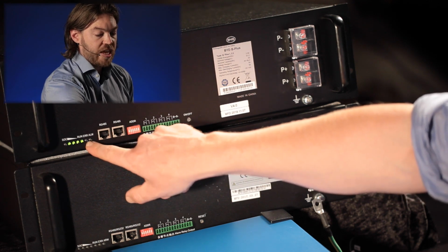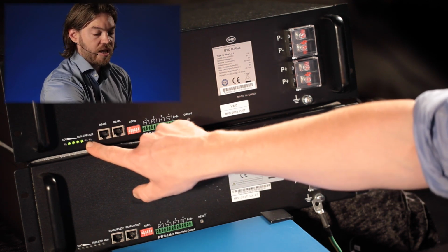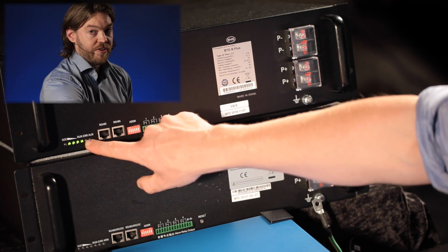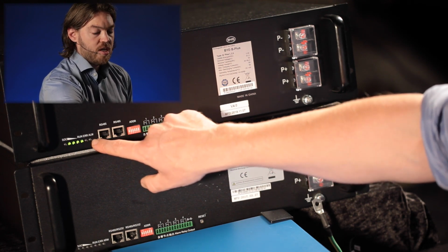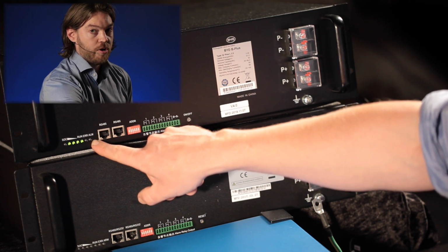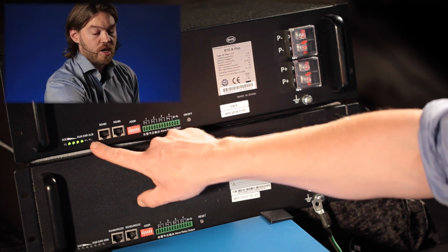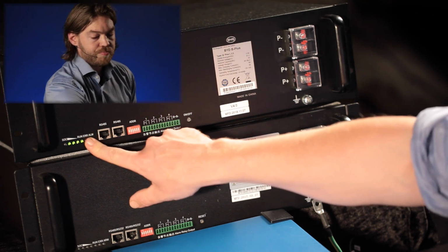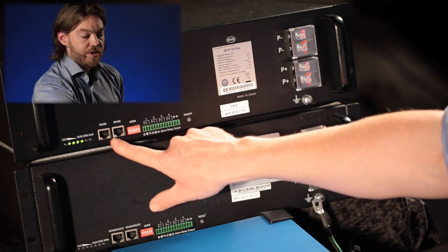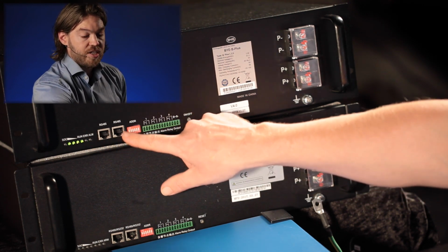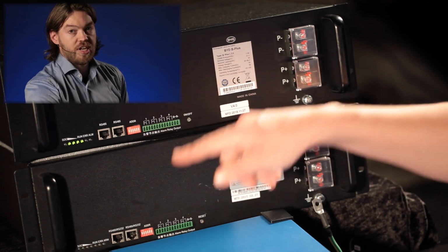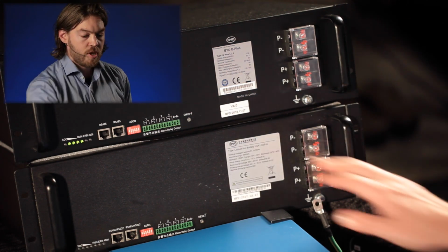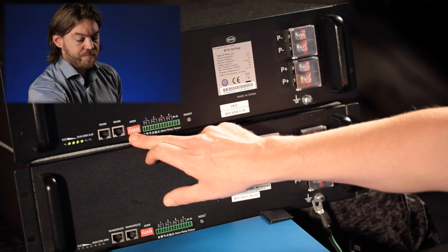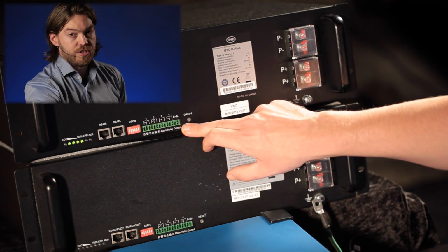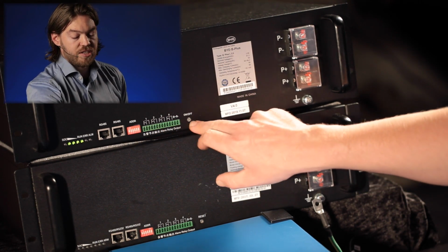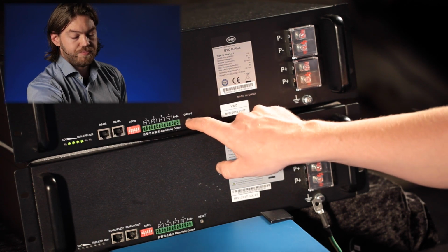Beside that there's an ERR point, and if this is red, the battery has failed and you'll need to contact BYD. There's another light next to it which can shine up orange - this is a soft error, which is usually correctable. To the right of those, there's the RS485 ports. These connect to other batteries and also connect to the BMU. Then we have the addressing point, and then some other connections which we don't use in this feature. Lastly, the on-off button on the right-hand side.